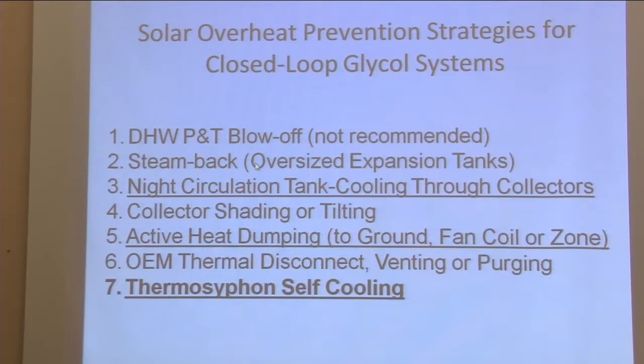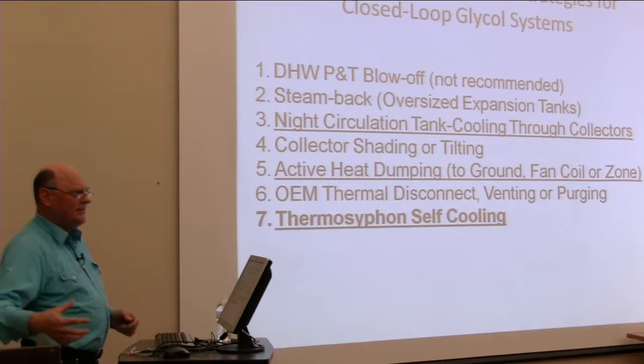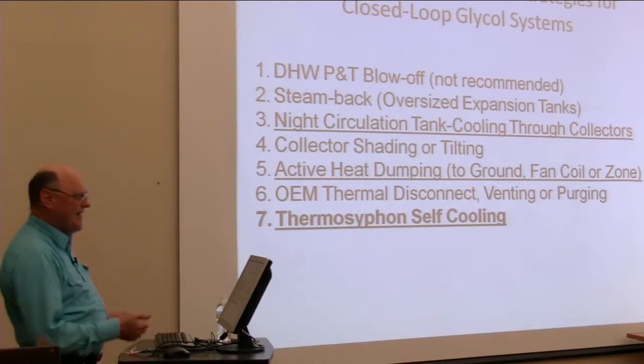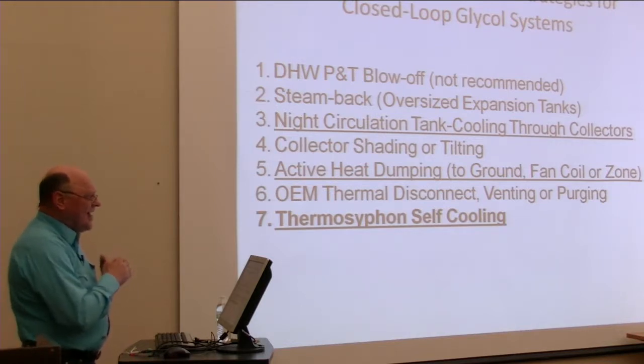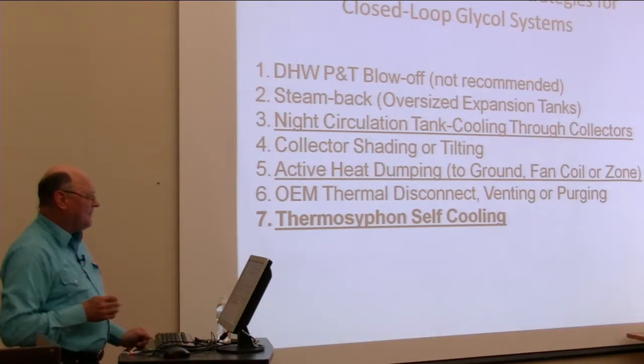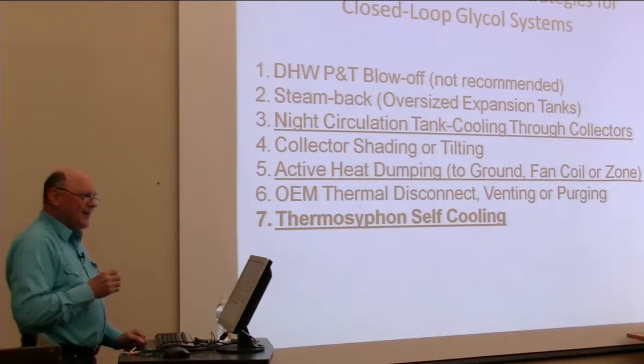There's something called steam back, where you actually allow the liquid in the collector to steam, and it turns to steam and goes into an oversized expansion tank and sits in the tank until sunset, and then the steam condenses and the liquid comes out of the tank. That's called steam back. I don't recommend using steam back as the overheat of last resort, because it does allow steam to boil in your collectors, and that actually boils the antifreeze in your collectors. And the more you boil your antifreeze, the older it gets, the more it ages, and the more acidic it becomes. So steam back I consider to be okay as a last resort. If everything else goes wrong, steam back's okay as a last resort.